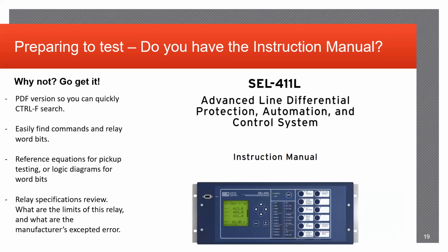Instruction manual. If you're getting into relay testing, the first thing they're going to tell you if you have any questions is, did you look at the manual? Because pretty much 99 times out of 100, you'll probably find your answer in the relay manual. It's a lot easier said than done because these relay manuals will be anywhere from like 600 to 1,000 pages of just everything to do with whatever relay you're testing.